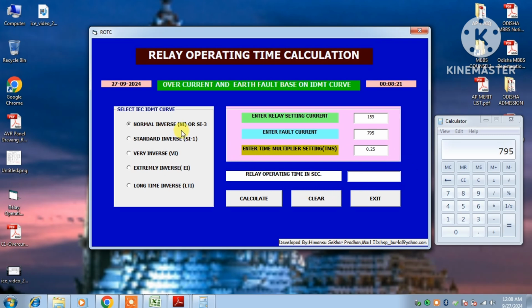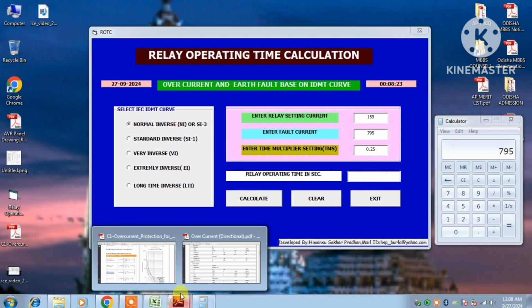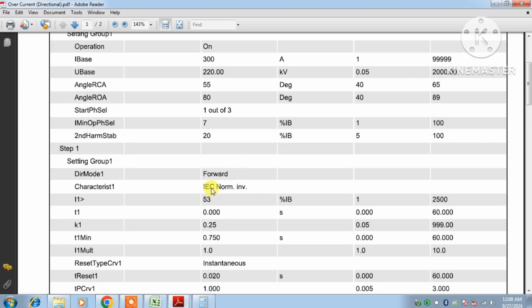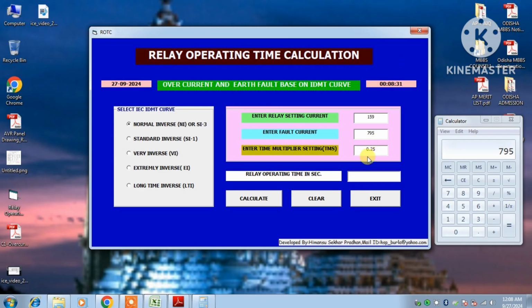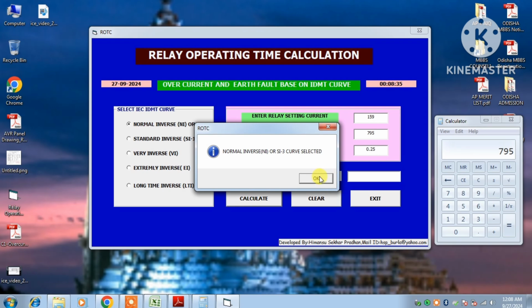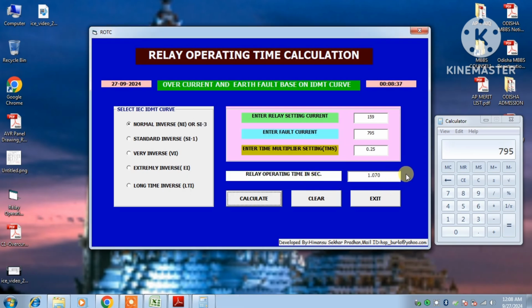As the given curve is IEC normal inverse, we'll select the IEC normal inverse curve and calculate. Now, if the fault current is 5 times the setting current, the relay will operate in nearly 1 second.